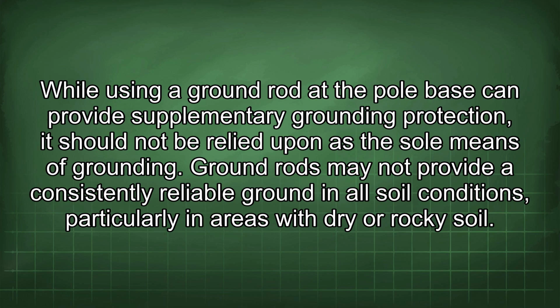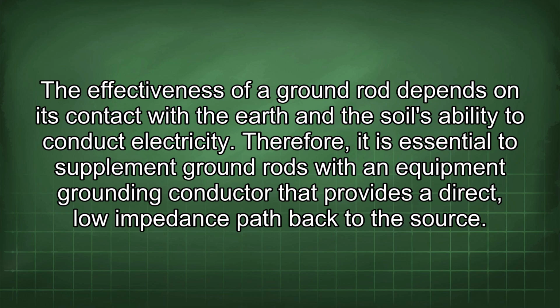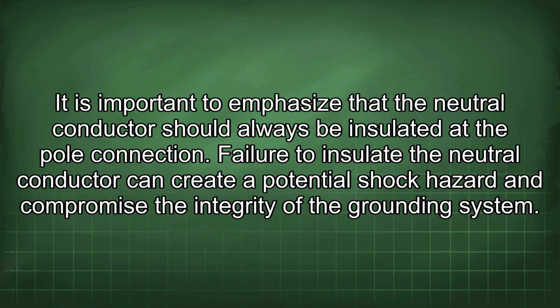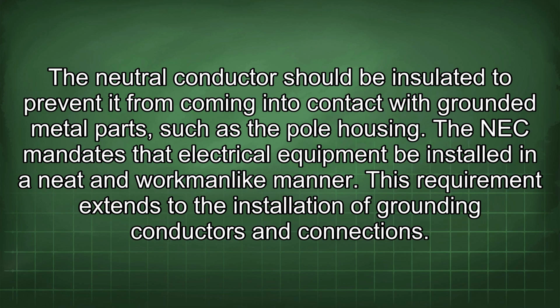Ground rods may not provide a consistently reliable ground in all soil conditions, particularly in areas with dry or rocky soil. The effectiveness of a ground rod depends on its contact with the earth and the soil's ability to conduct electricity. Therefore, it is essential to supplement ground rods with an equipment grounding conductor that provides a direct, low-impedance path back to the source. It is important to emphasize that the neutral conductor should always be insulated at the pole connection. Failure to insulate the neutral conductor can create a potential shock hazard and compromise the integrity of the grounding system. The neutral conductor should be insulated to prevent it from coming into contact with grounded metal parts, such as the pole housing.